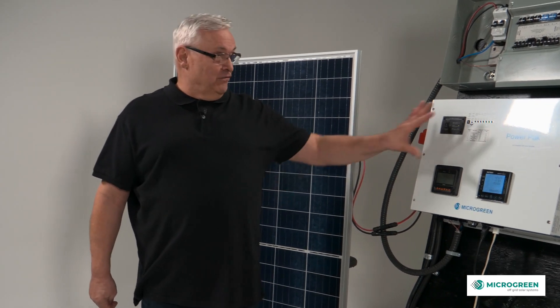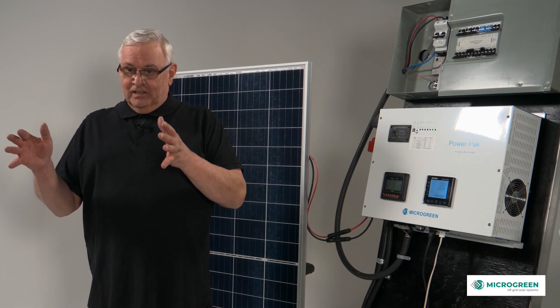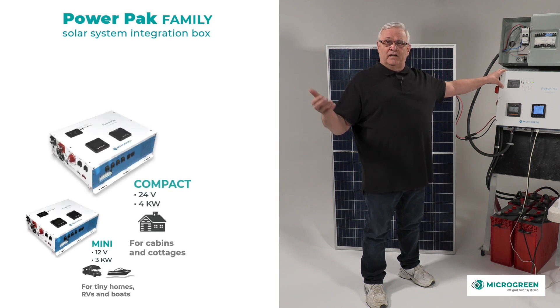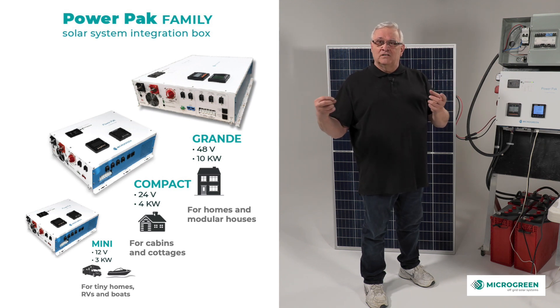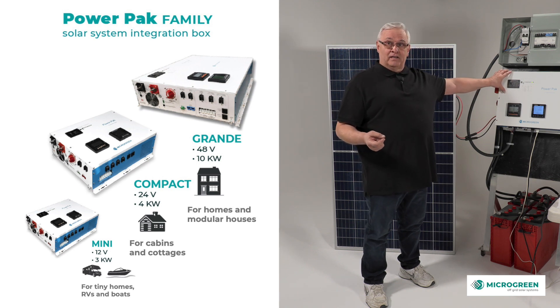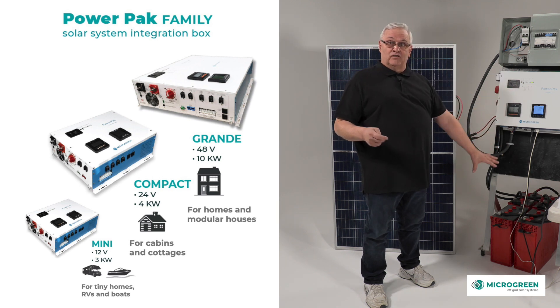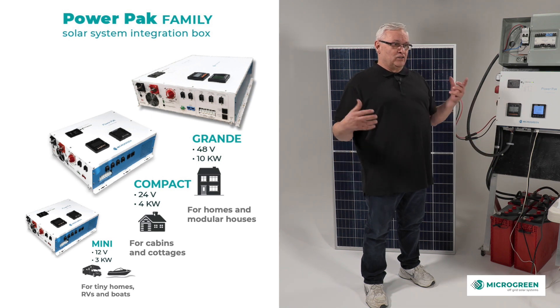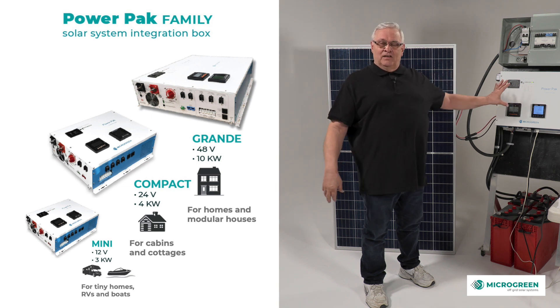There are three versions of the Power Pak. Once we got everything into a box and realized the 4kW was the average cottage size, that led us to create a mini, a compact, and a Grande. The mini is a 12-volt system for cabins, RVs, boats, and tiny homes — you can get DC 12-volt objects and hook up nicely to the mini system. The compact is a 4-kilowatt, 24-volt system — the higher the wattage, the higher the voltage has to be. At 24 volts and 4 kilowatts, you can run what most houses or cottages have: a deep well pump, a fridge, fans, lights.